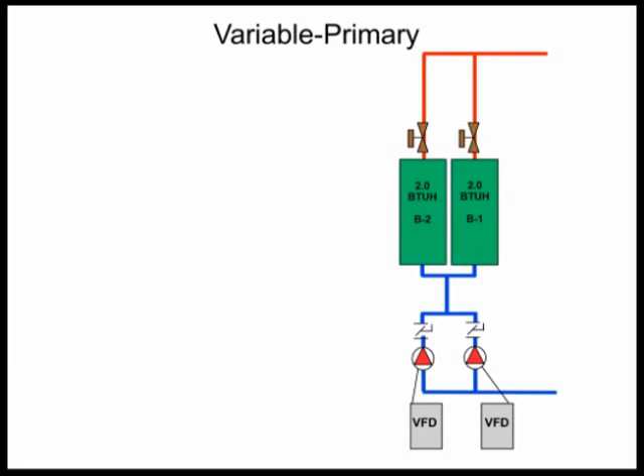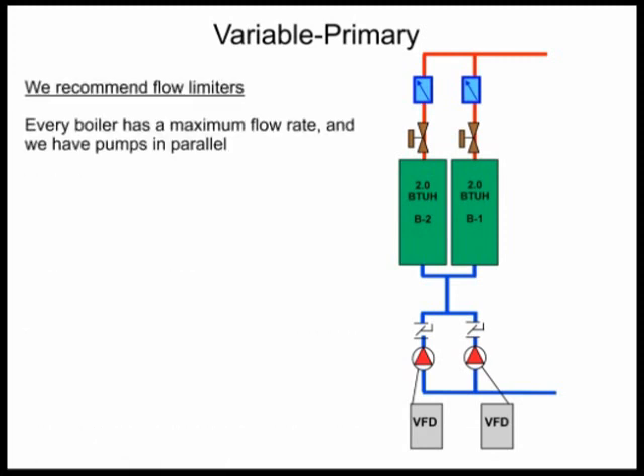Now that we know we need isolation valves, is there anything else we might want to put in this system for proper operation? We have two pumps at the bottom and they're in parallel. Is there any chance those two pumps could come on together through one boiler? The answer is yes — the pumps are controlled by the building management system or the variable speed pump controller, not by the boilers. There are also VFDs. Do those VFDs have bypasses or manual mode? An operator could turn both pumps on and overflow the boilers, and with too much velocity you can erode the tubes and ruin equipment. For a little bit of money, you can put an automatic flow limiter in there. We highly recommend them — they should not be optional. Every boiler has a maximum flow rate, and with pumps in parallel you can always end up having trouble.